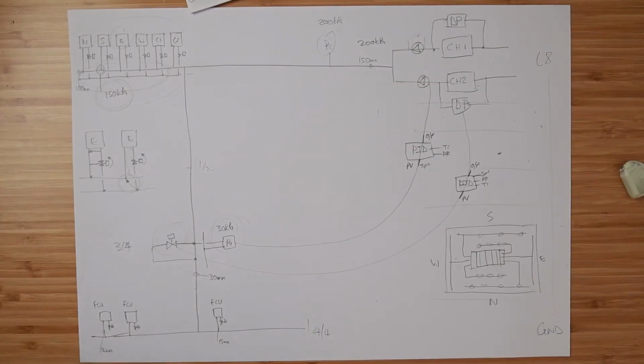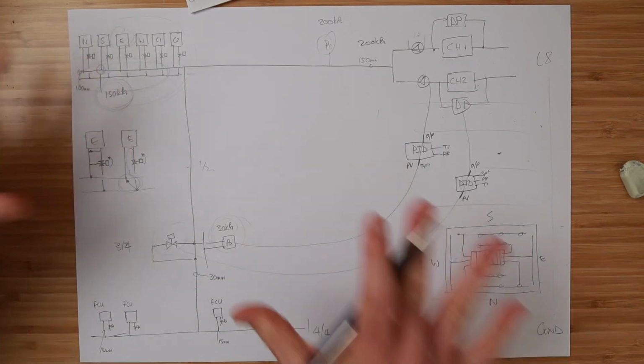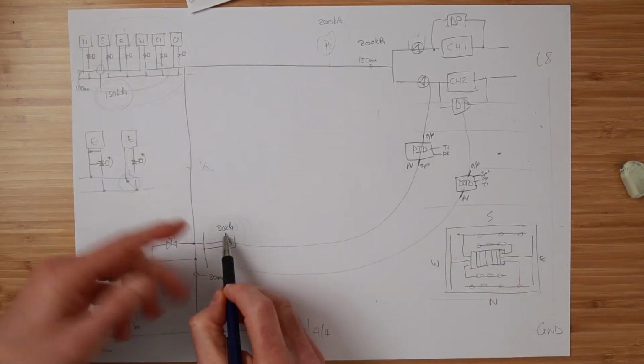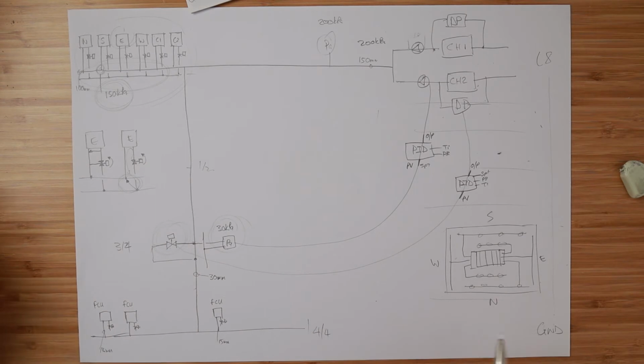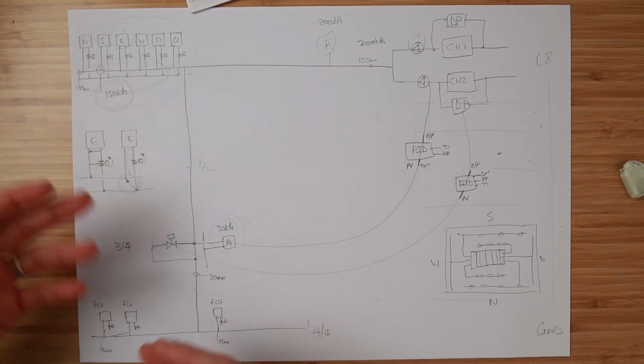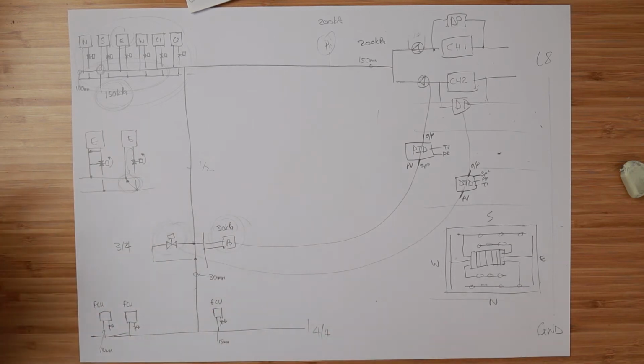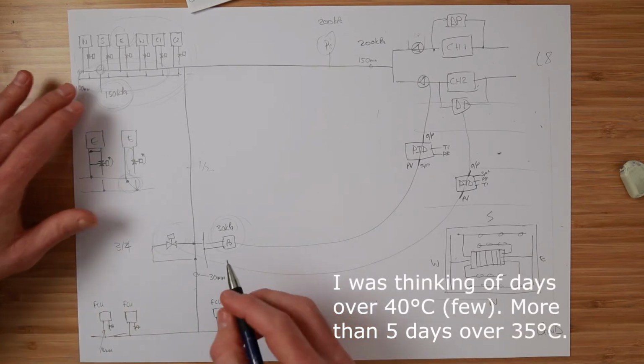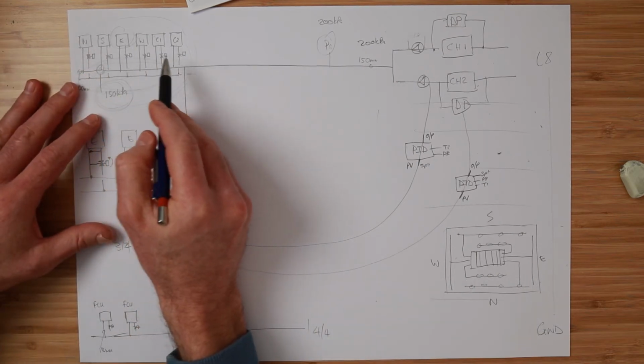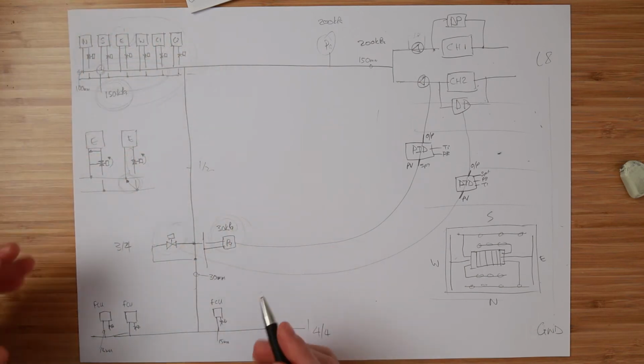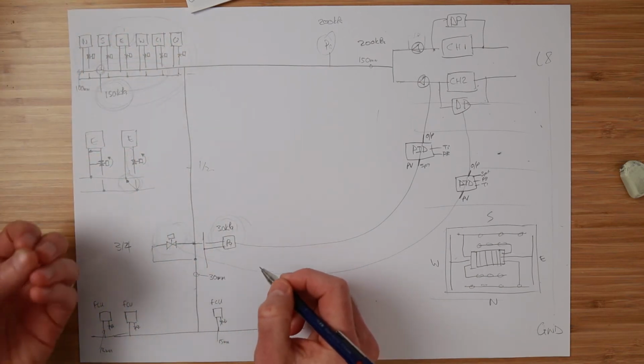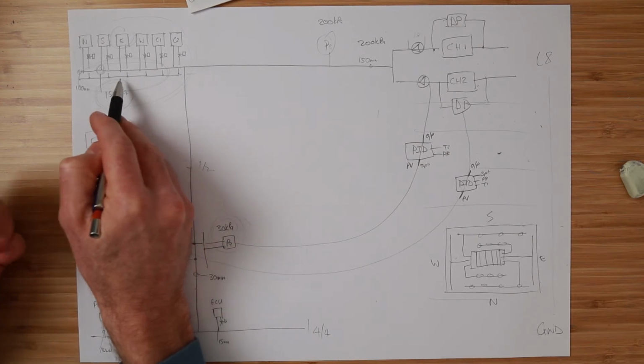Because when it's properly balanced and everything's open and it sits like this, the 30 is sort of okay, but every other day that's not full load, here in Melbourne, Australia, we probably only have a design day, where it's over 35 degrees Celsius, probably like, let's say 5 times a year, or 5 times through summer. It's not the normal. So when we're not in full load and the valves aren't fully open and they're open to all sorts of different amounts and there's different things going on in different places, this pressure here probably is not a true representation of what's going on over here.